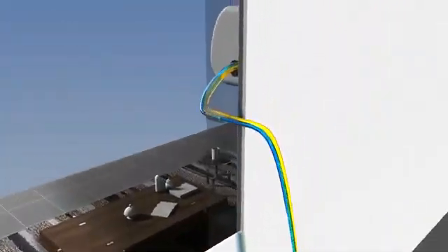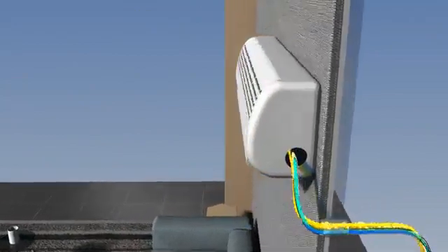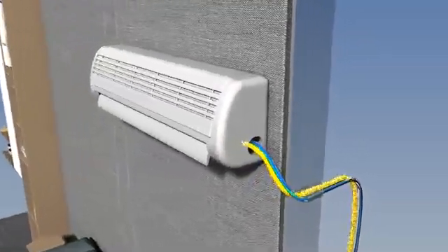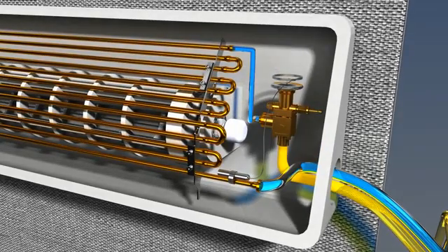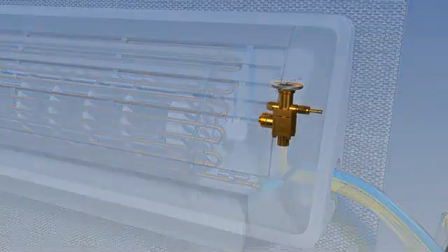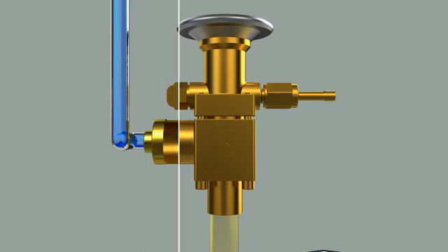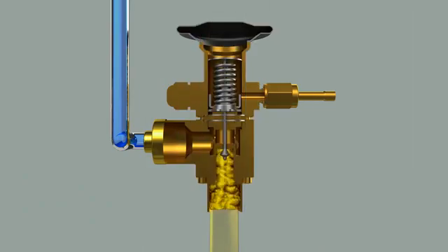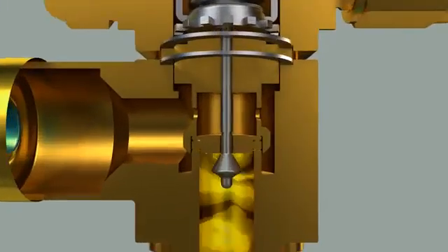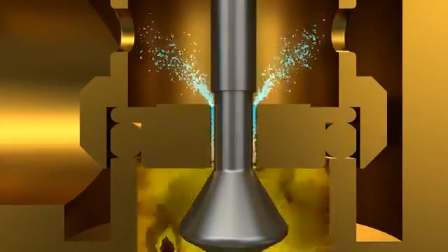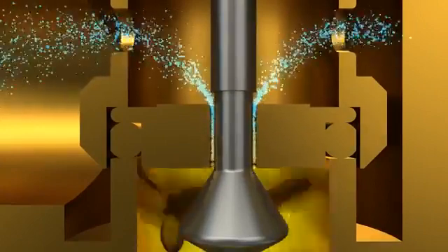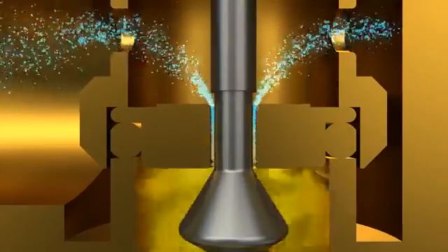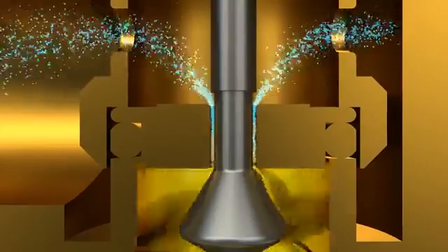Although the refrigerant has thrown off some of the heat as it passes through a condenser, it is still hot, with a temperature of about 50 Celsius. The refrigerant in high temperature and high pressure liquid form flows into the expansion valve. The refrigerant which used to flow in large space now passes through a narrow area, and its pressure drops as it goes. When the pressure drops, temperature drops dramatically as well. The cool refrigerant is now sent to an evaporator.